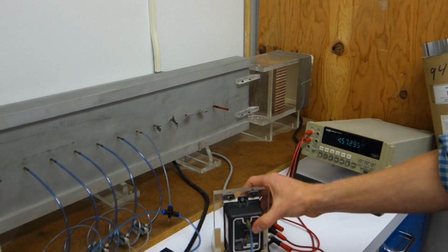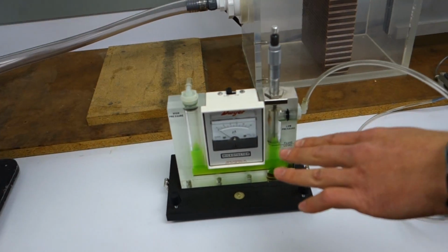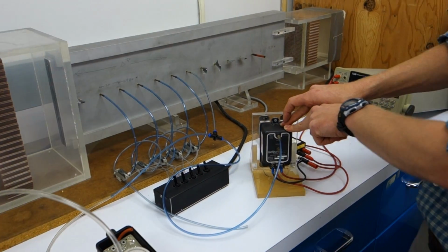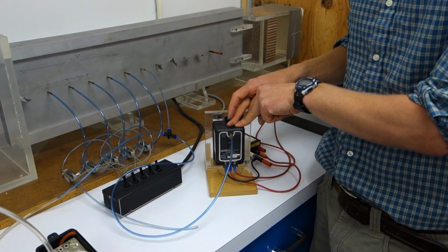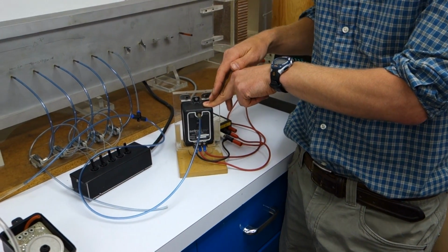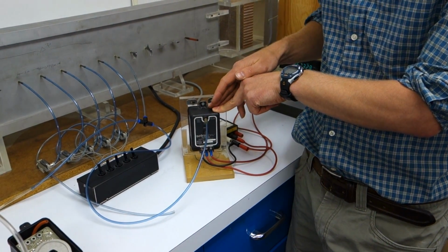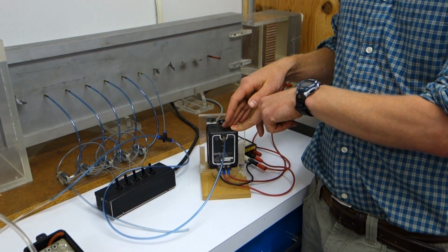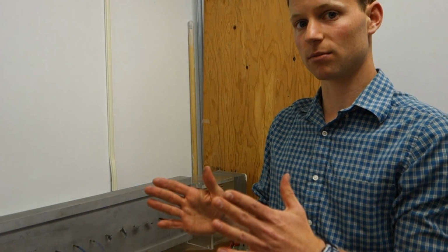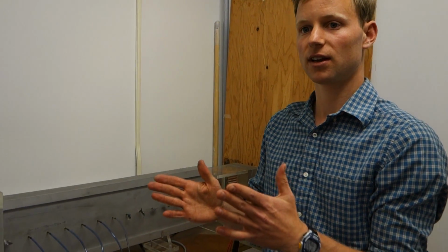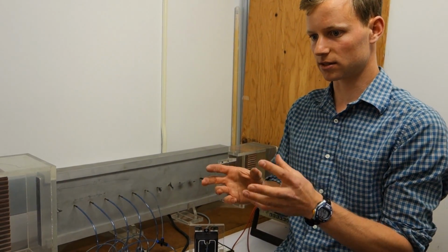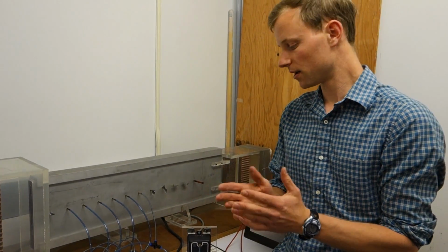So we're going to use our microtector to calibrate our capacitive pressure transducer. Now, I think the same principle applies to the other transducers we saw on the other side of the lab, where it's a pretty cheap device. There are other types of electronic pressure transducers. There's piezo-resistive and piezoelectric, where if you apply a force on a piezoelectric or piezo-resistive material, you'll get a change in voltage or a change in resistance, respectively, across this substance, and you can pick that up with a circuit.